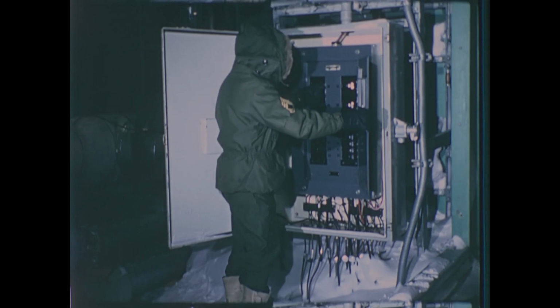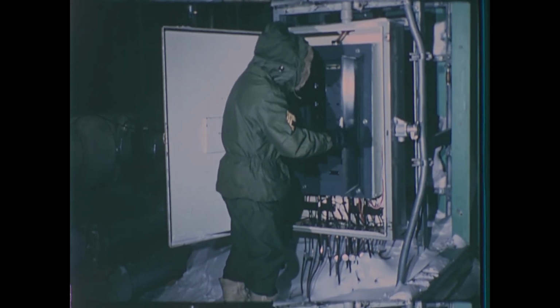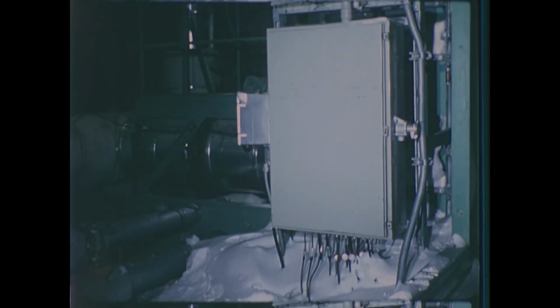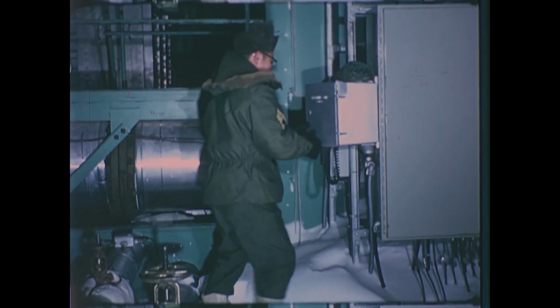With primary system up to pressure and temperature, the equipment operator goes to the condenser deck. He ensures proper lineup of power to the condenser freeze protection system. Roll-up doors on the condenser building may now be opened to provide an adequate supply of air. In preparation for an operational check of condenser controls located at the plant console, the equipment operator establishes communications with the control room operator.